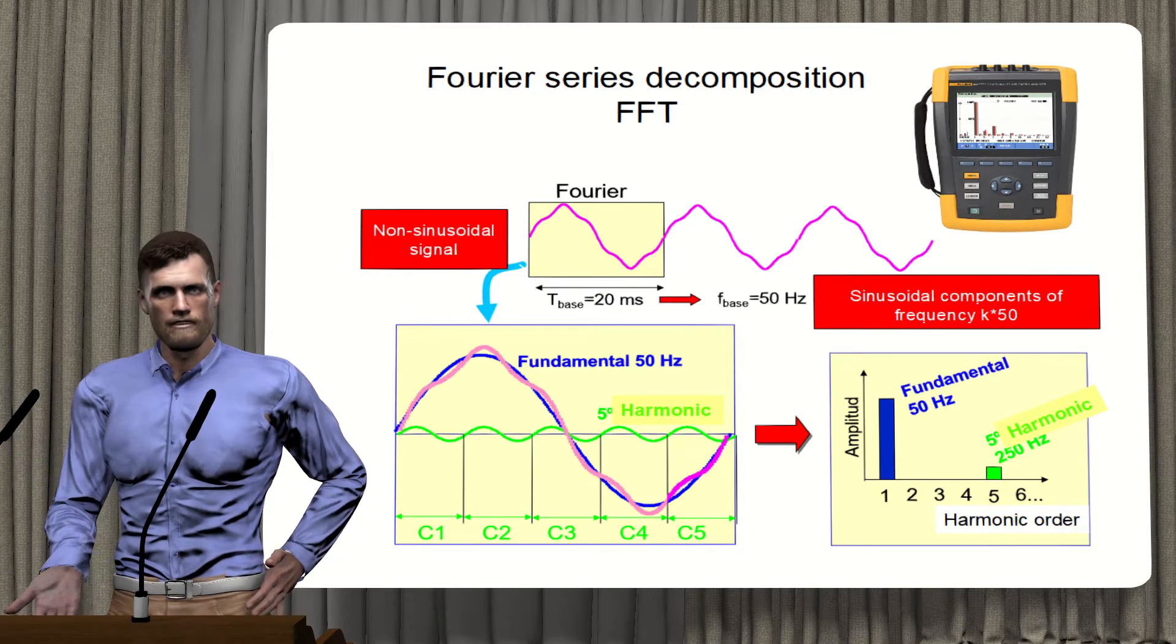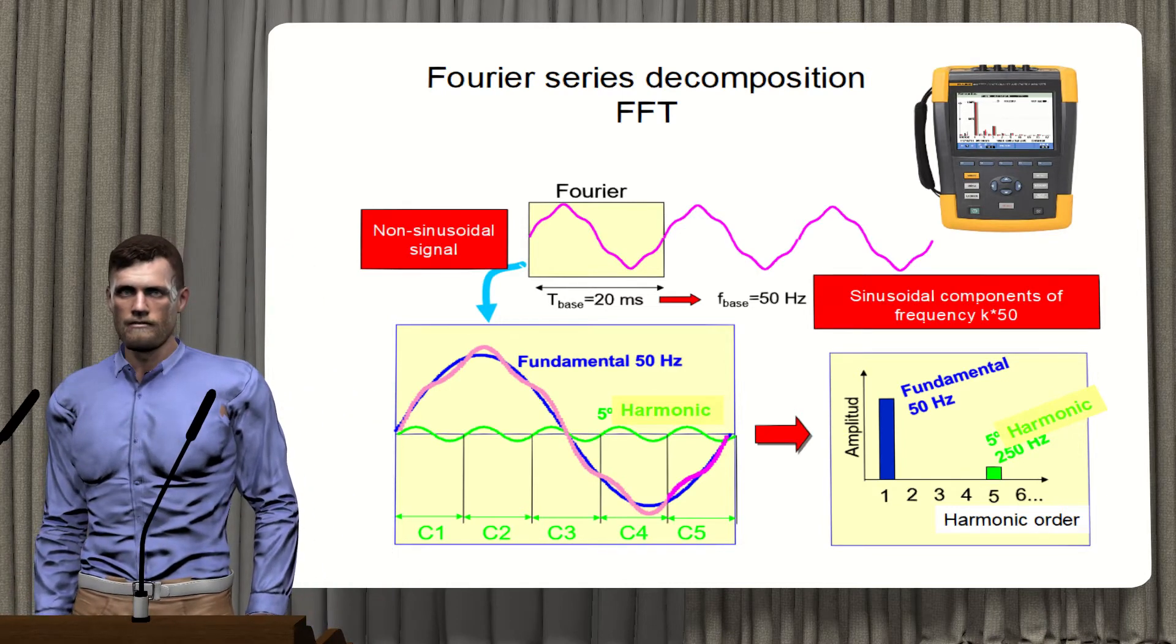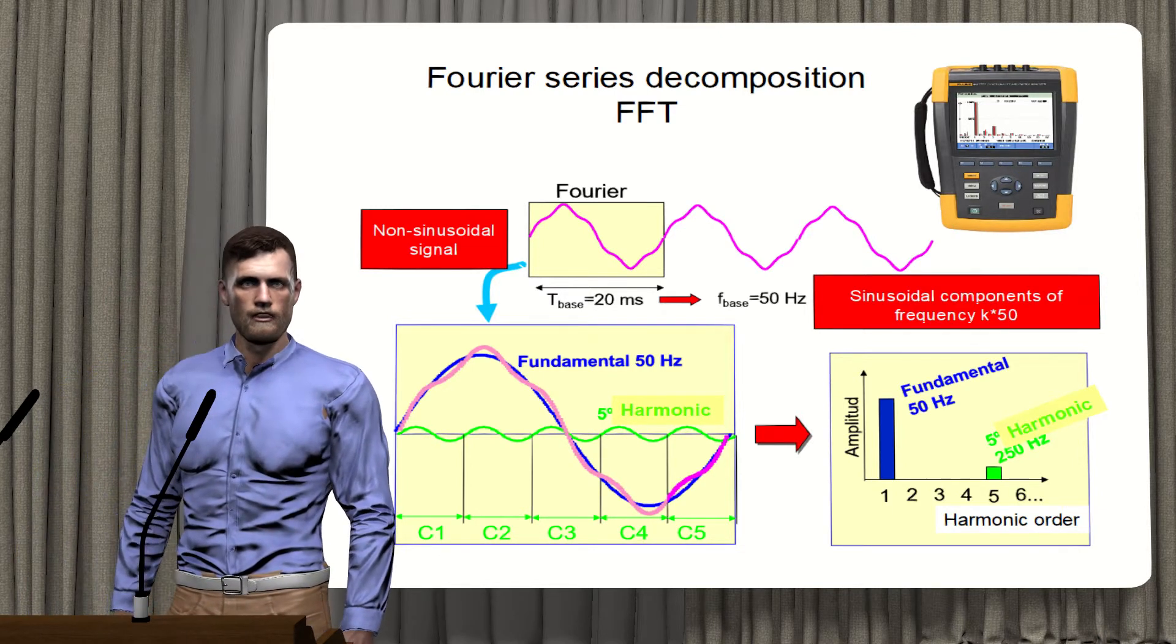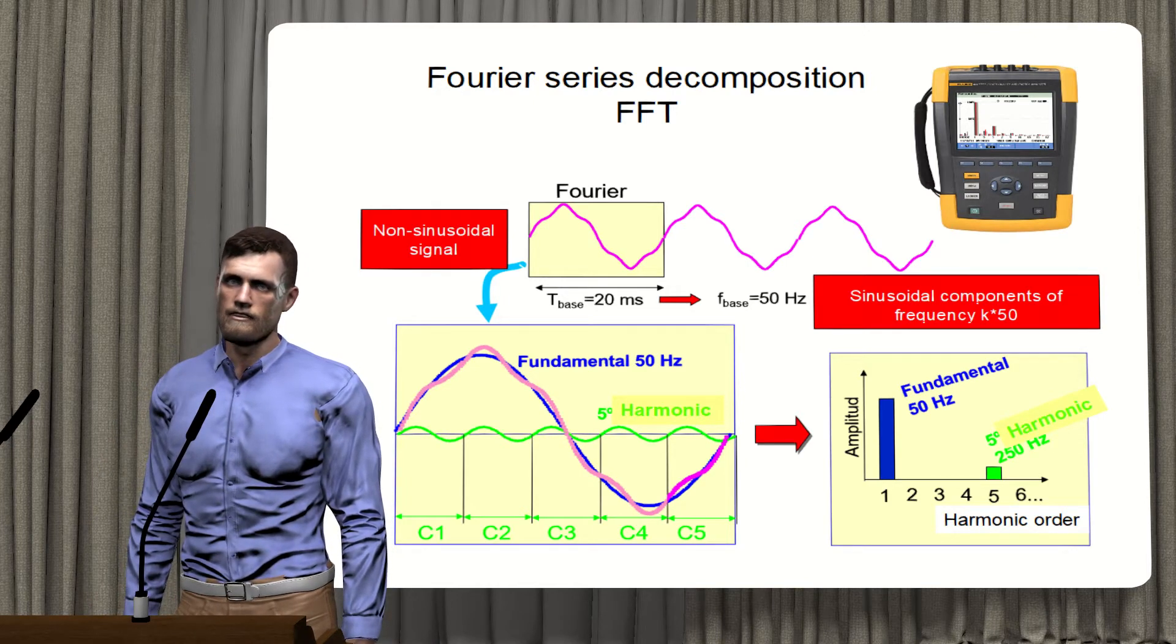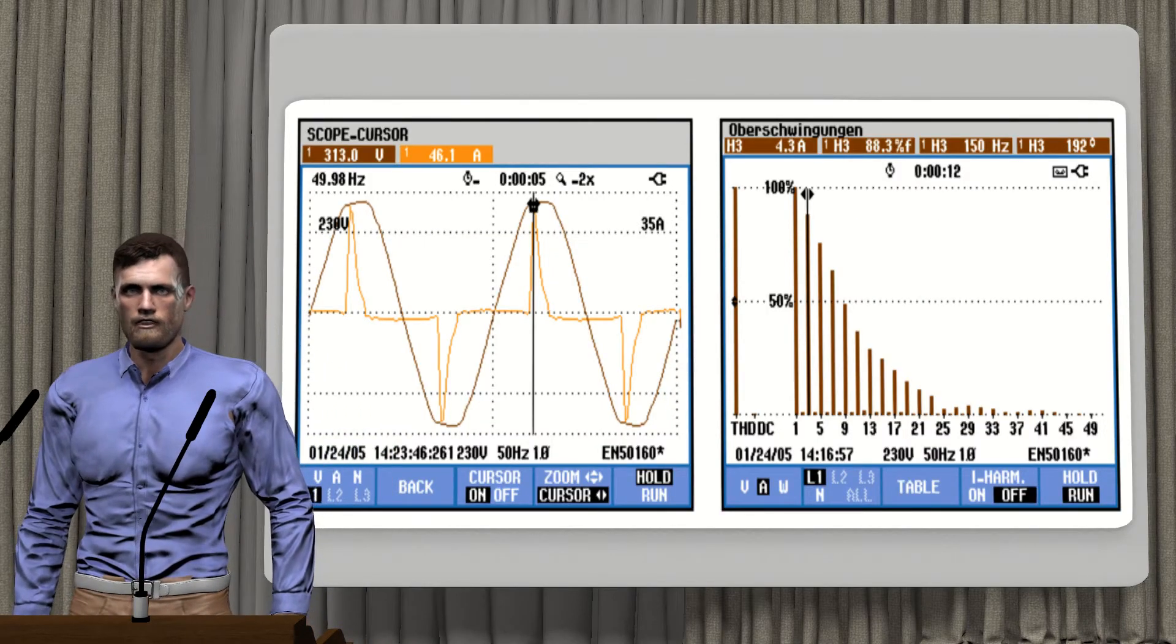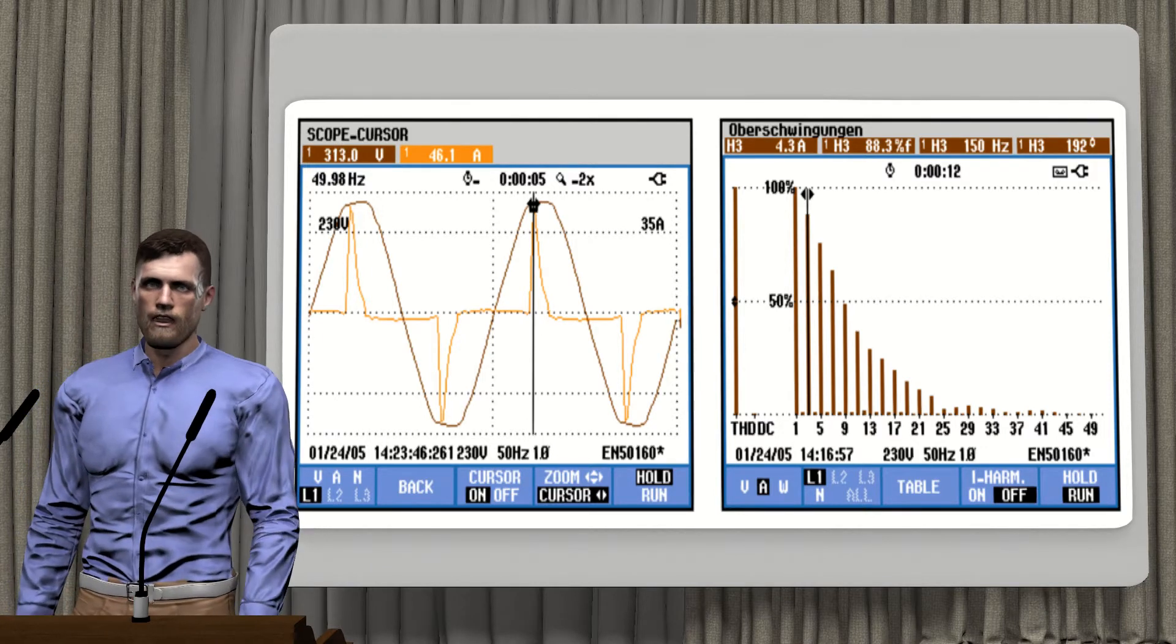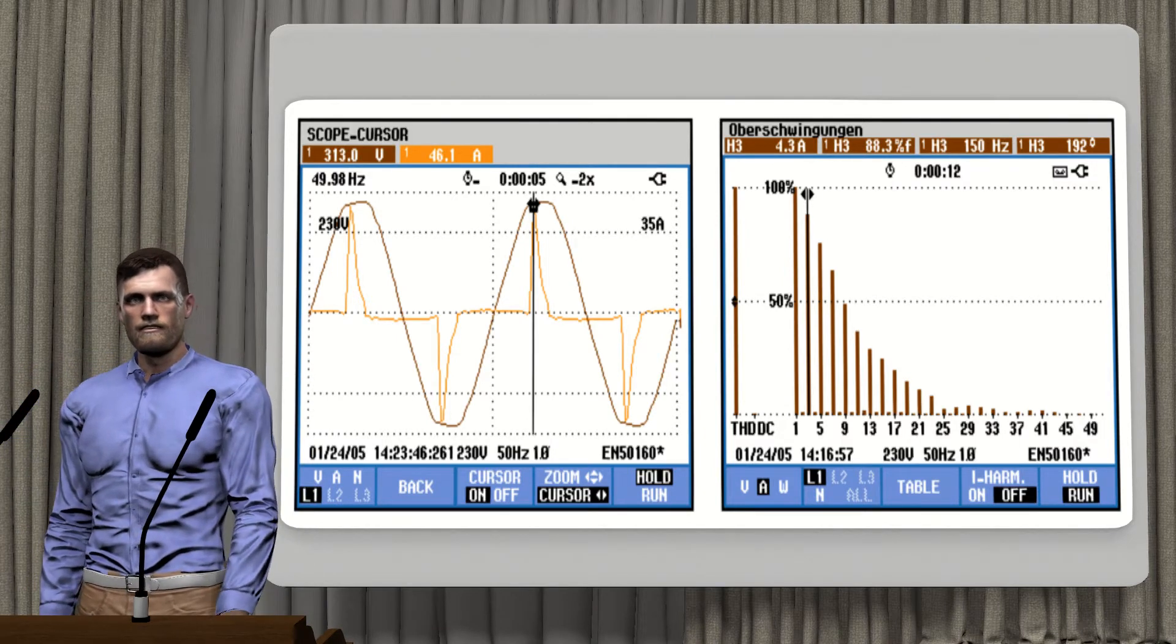These effective values can be represented in a typical bar graph where a number called order is shown on the horizontal axis, which for the fundamental component is number 1, for the harmonic of 100 Hz is number 2, for the harmonic of 150 Hz is number 3, and so on. And the vertical axis represents the effective value of the fundamental component and the harmonics, either in absolute value, for example in volts or amperes, or as a percentage value, where the fundamental component would take the value of 100%, and the harmonics a percentage value in relation to the fundamental component.